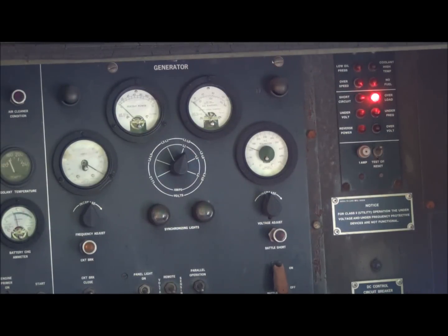Okay, after several minutes of testing, I've been able to test the overloads on each of the 3 phases. All 3 were just fine. I set the load at about 140% of rated current on each phase, and each one tripped within a few minutes.